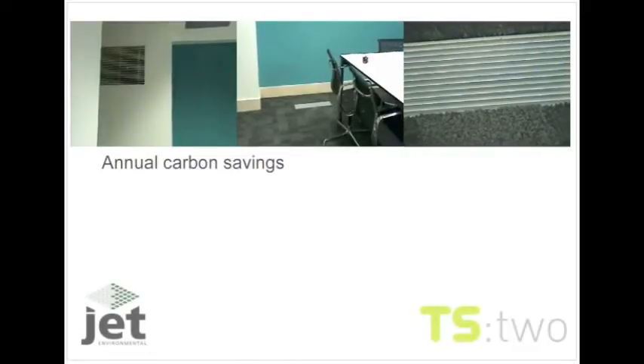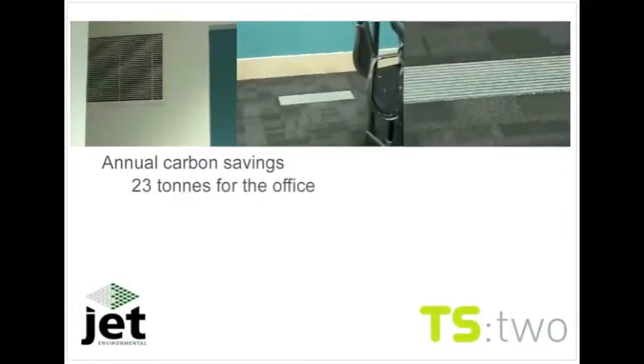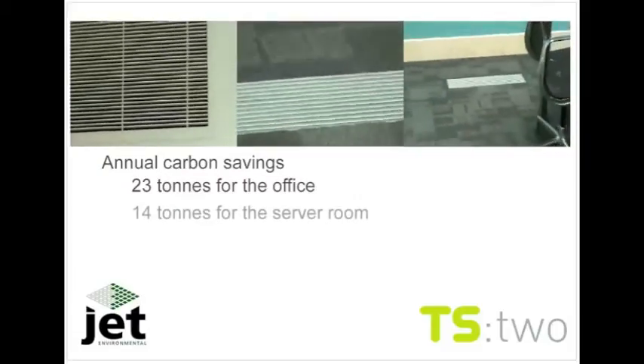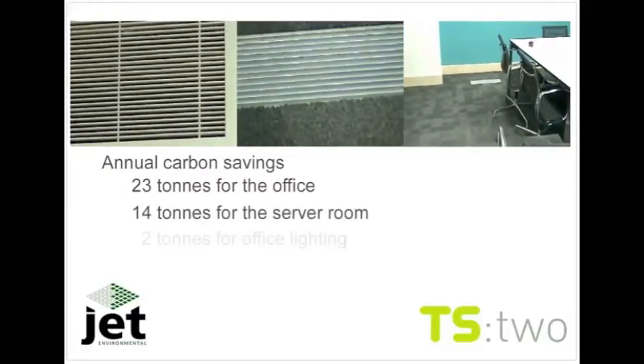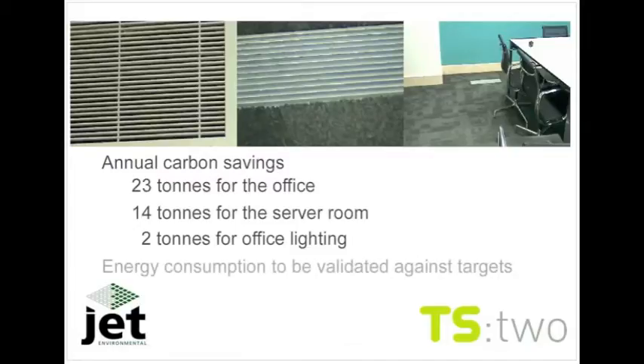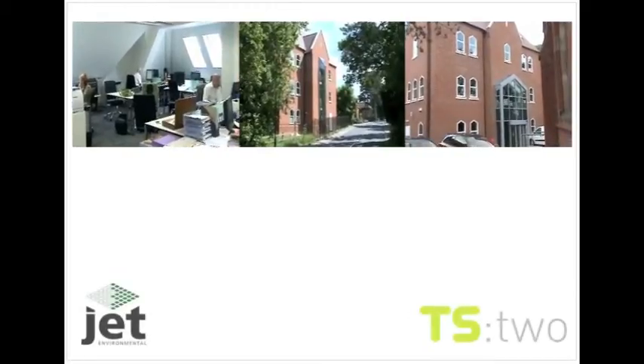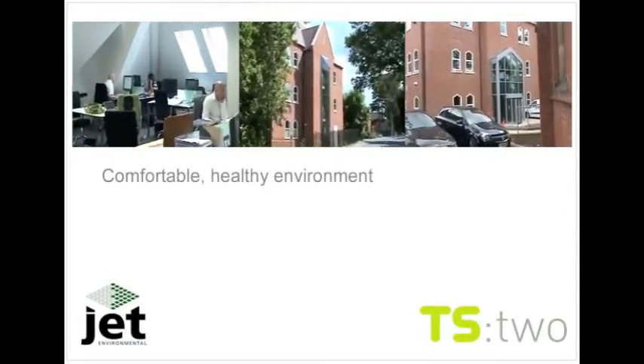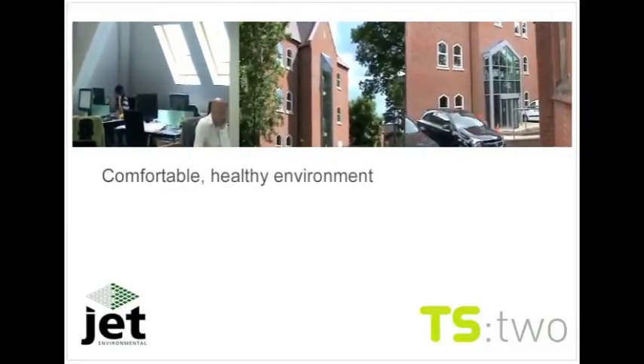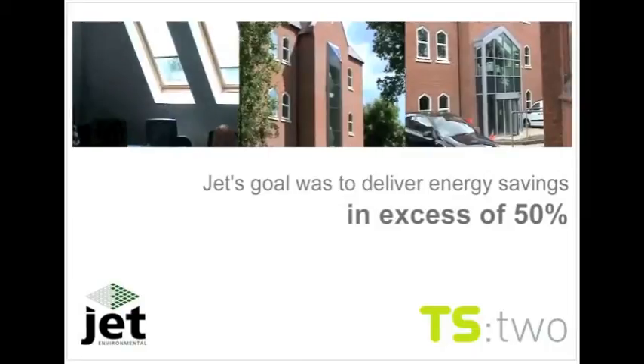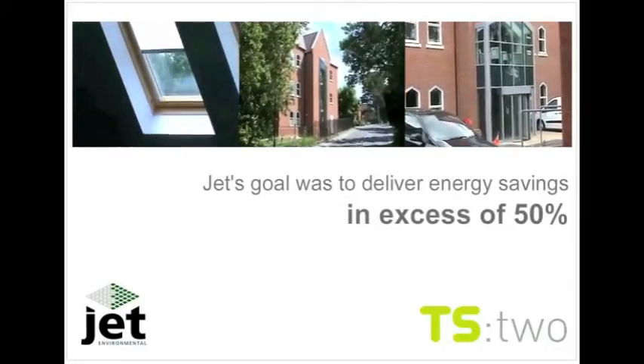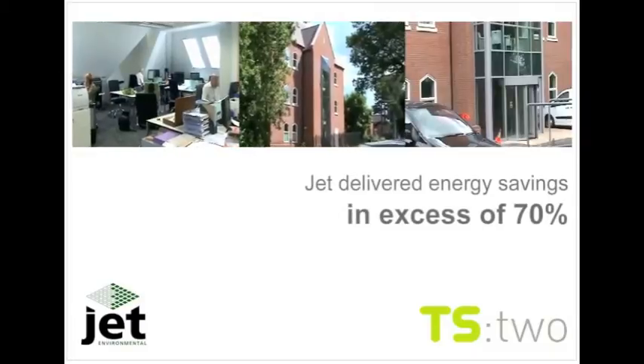The annual carbon savings have been calculated as 23 tonnes for the office air conditioning, 14 tonnes for the server room AC, and 2 tonnes for the office lighting. Inclusion of energy and hours run meters linked through the BMS allows energy consumption to be validated against targets. The solution has proved to be a great success. A more comfortable, healthy environment for its occupants without annoying drafts. The Jet system is exceeding the energy-saving target set by Candlelight Property, delivering savings in excess of 70%.